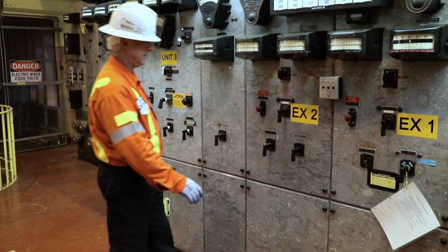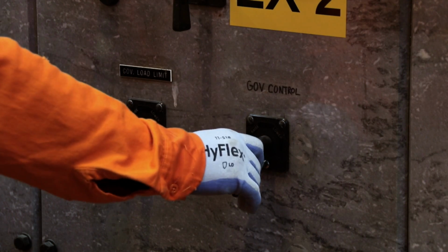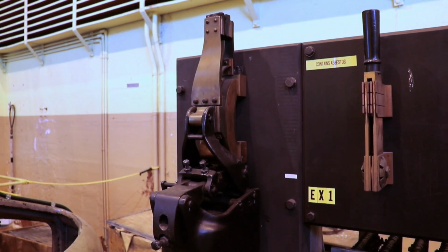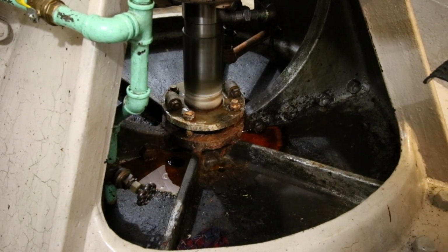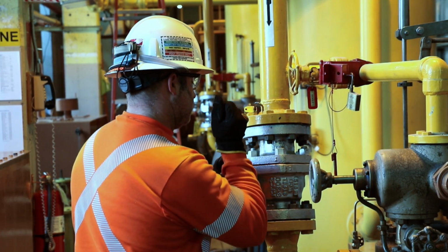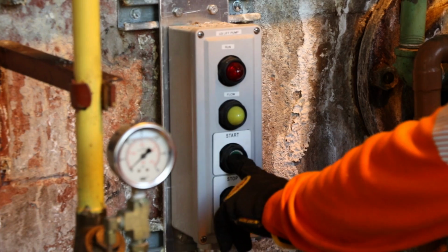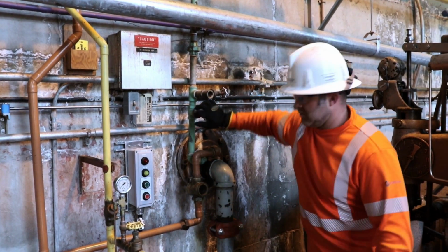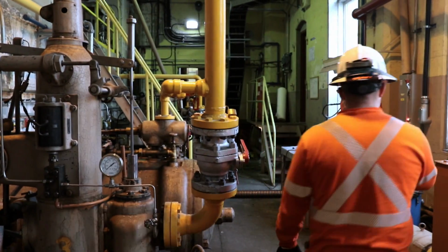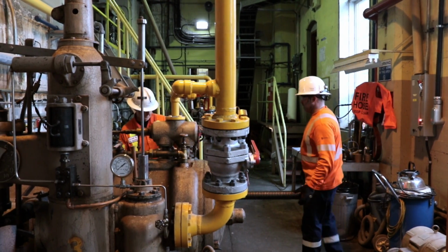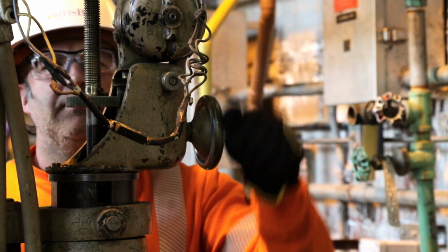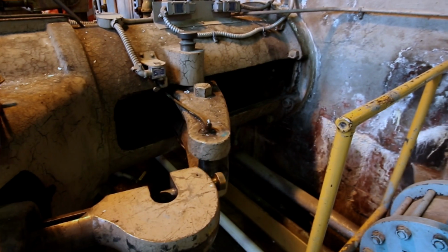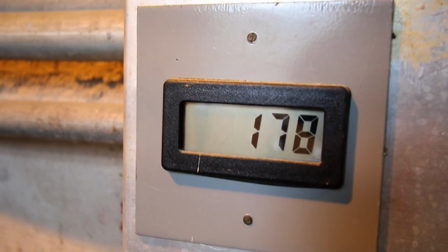The old units here at Upper Bonnington all have to be manually started and stopped, and the process literally is a 50-step checklist that takes 3 tradesmen. We need to initiate excitation voltage by starting our water wheel exciter and visually confirming that the unit is spinning. Next, we need to open the governor oil valve and confirm flow, then start the bearing oil pumps, and then open the cooling water valve. Once cooling water is flowing, 2 tradesmen are required to manually turn the hand wheel to free the governor arm. They then manually open the wicket gates to set the unit speed to approximately 179 RPM.